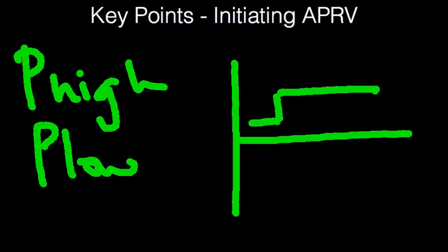The P high would represent the inspiratory time here. While P low will be the level here where the patient's during the expiratory phase. P high is pressure high, and P low is pressure low. The next term would be T high, which is the time that the patient's at the P high level, and T low, which is the time the patient's on the P low mode.